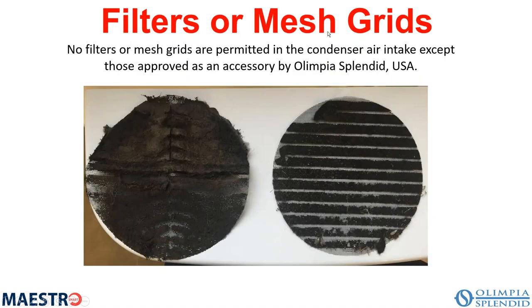Makes sense. The other thing we don't recommend is that they install a mesh or filter in the duct, because this result, you can see here, all this buildup was because the consumer never cleaned it, never had it cleaned once a year. And of course, this didn't take long, because you can see how small the holes are.